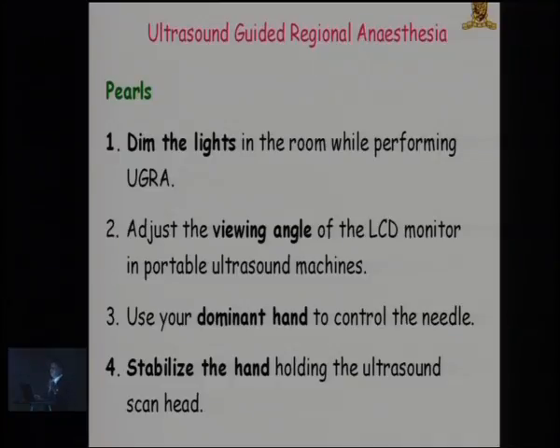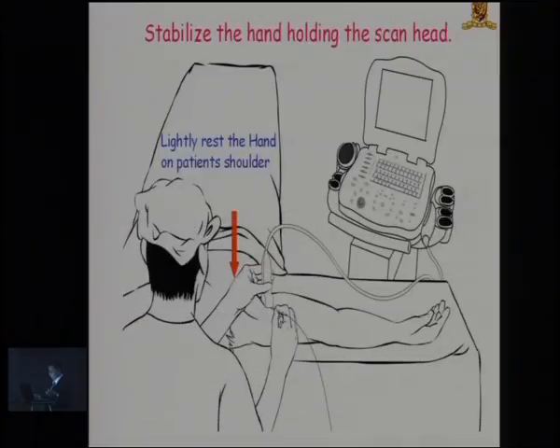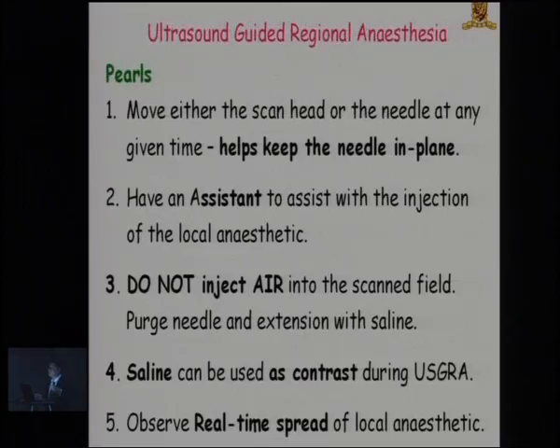Stabilize the other hand that's holding the probe, because you can imagine you can't move two things at the same time. If you move both at the same time, then you're not going to see the needle. So if you see in this case, when we do the axillary block, the operator here has got his hands rested on the patient so that the ultrasound probe is stable, and then you just advance the needle. So move one thing at a time. Don't move both at the same time. Now, because you're using both hands, you need an assistant to inject the local anesthetic.